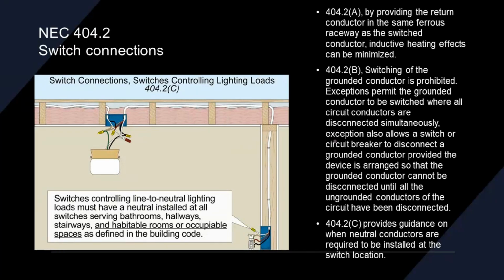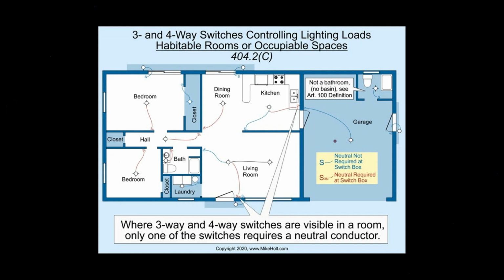404.2c tells us when neutral conductors are required to be installed at a switch location. So 3- and 4-way switches controlling lighting loads in habitable rooms or occupiable spaces, you have to have a neutral. So if you'll look at these red ones, the dining room is not considered habitable. Nope, it is. Bedroom, it is.